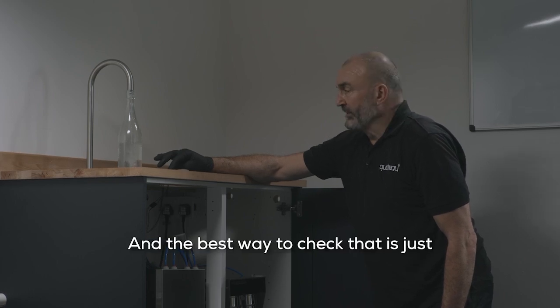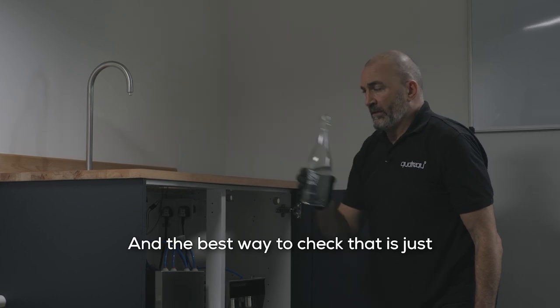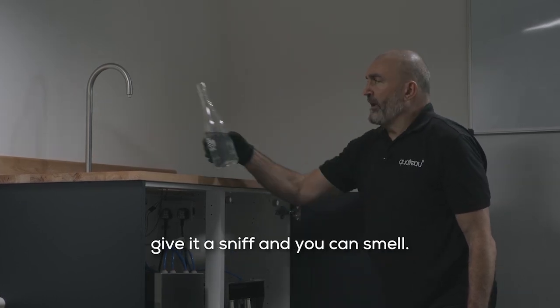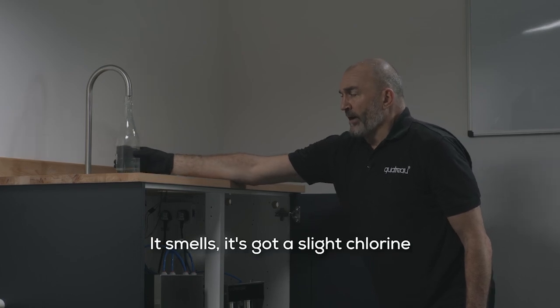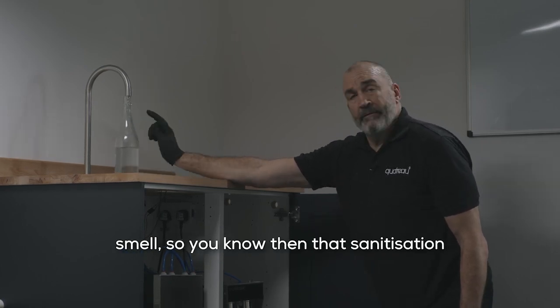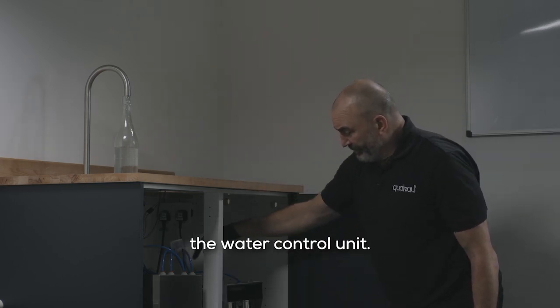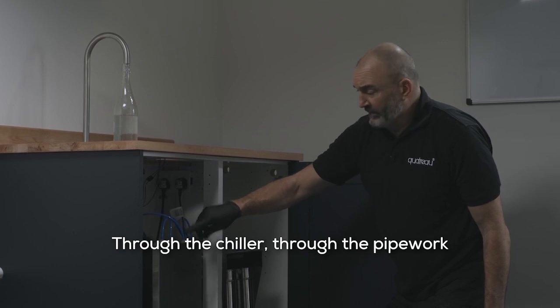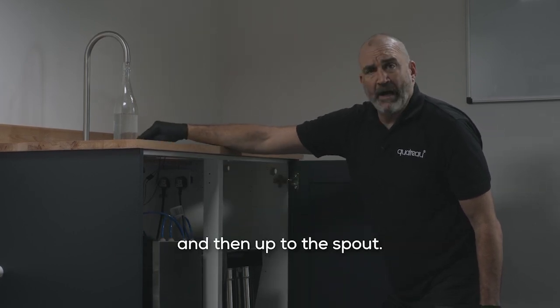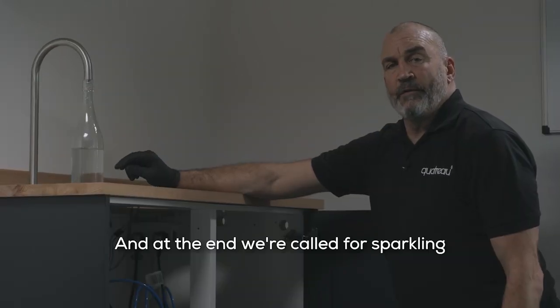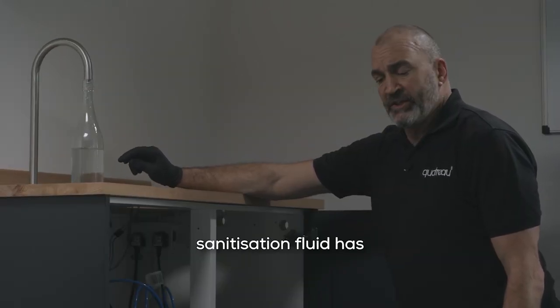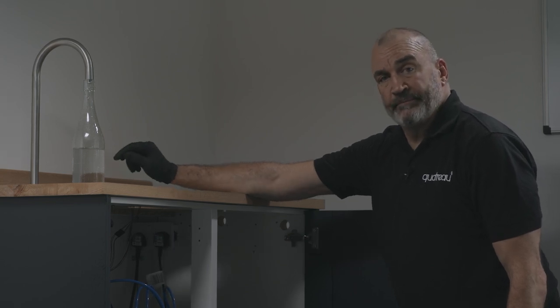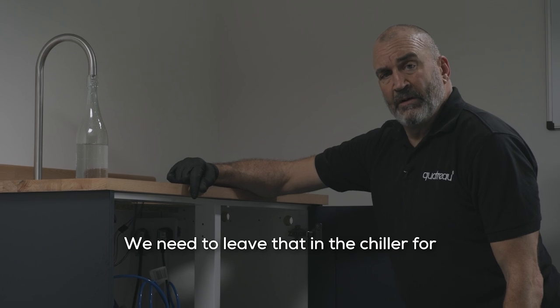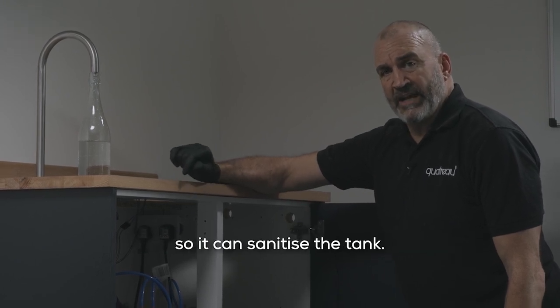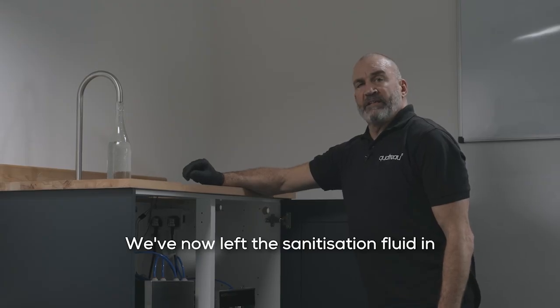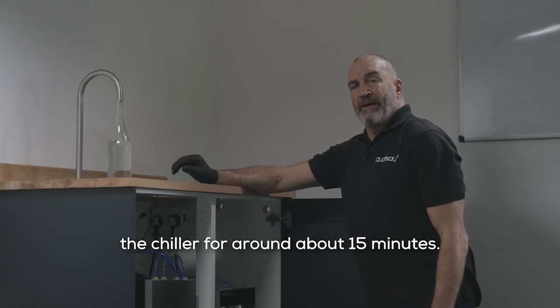And the best way to check that is just give it a sniff and you can smell. It's got a slight chlorine smell, so you know then that sanitisation fluid has gone through the water control unit, through the chiller, through the pipework, and then up to the spout. And at the end, we'll call for sparkling water just to make sure that the sanitisation fluid has gone through the whole system. We need to leave that in the chiller for about 10 to 15 minutes, just so it can sanitise the tank. We've now left the sanitisation fluid in the chiller for around about 15 minutes.